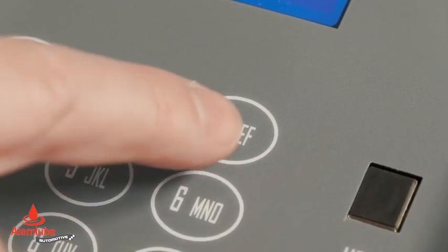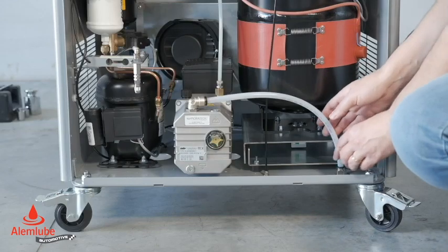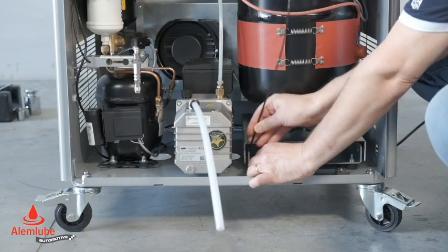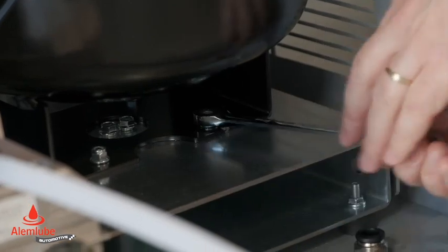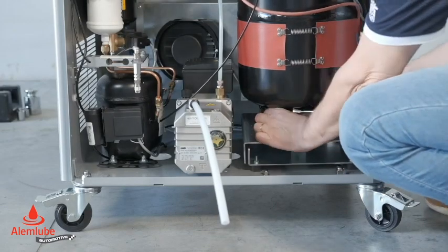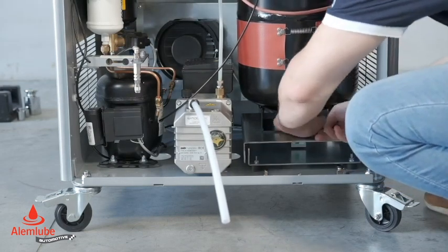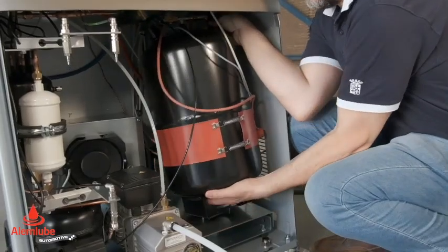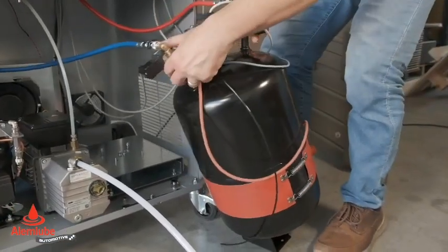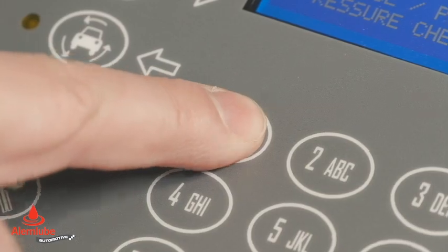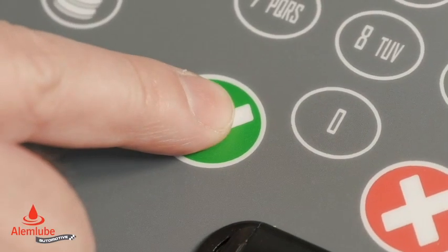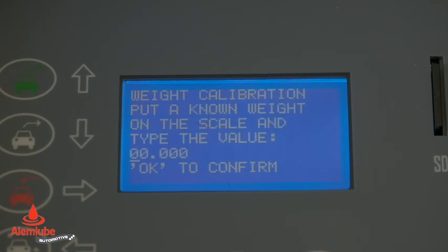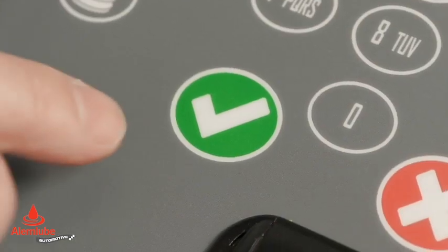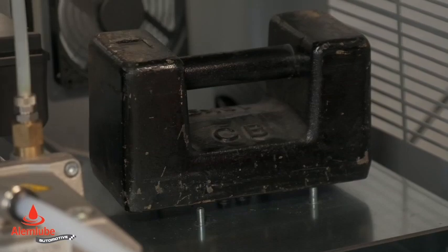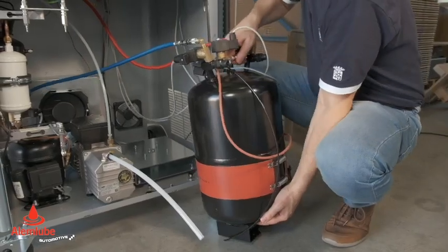By typing 3 in the maintenance section, you enter the balance calibration menu. Remove the cylinder from the scale so that the scale is completely empty. Select 1 to start cylinder scale calibration. Press enter to confirm the 0 value. Once the 0 has been stored, apply a sample weight, for example 10 kilograms, to the weighing pan. Type 10 kilograms on the display and press enter to store the second calibration point. Remove the 10 kilogram weight. Cylinder calibration is complete. Refit the gas bottle.